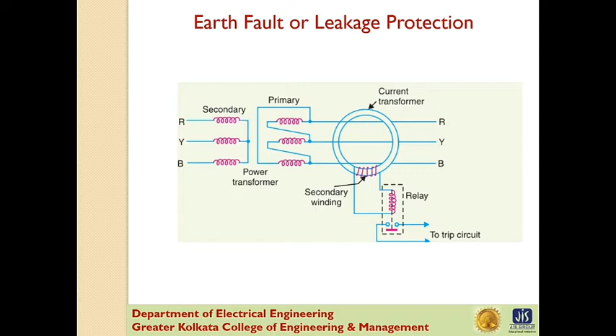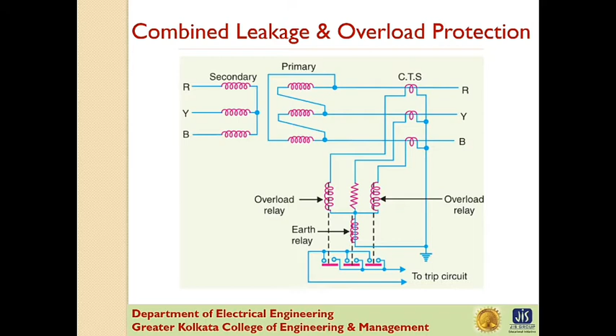Next is the combined leakage and overload protection. The core balance protection described in the previous slide suffers from the drawback that it cannot provide protection against overloads. If a fault or leakage occurs between phases, the core balance relay will not operate. It is usual practice to provide combined leakage and overload protection for a transformer. The earth relay has a low current setting and operates under earth or leakage fault only. The overload relays have a high current setting and are arranged to operate against faults between the phases.